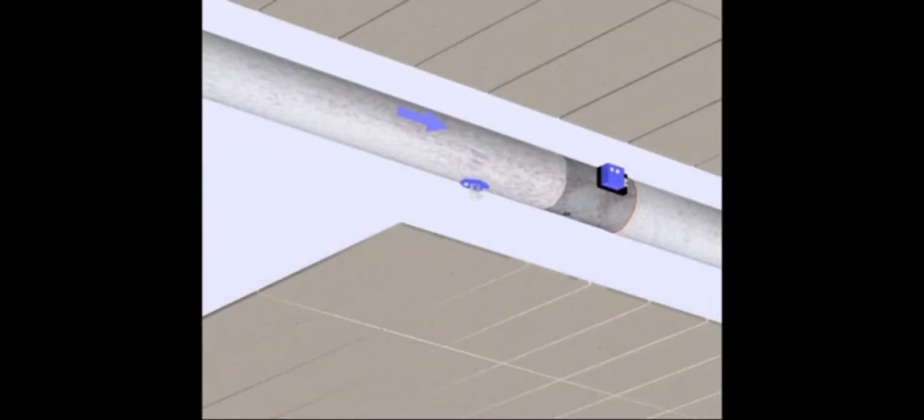The measuring point for the differential pressure sensor must be positioned at 1.5D away from the damper axle.